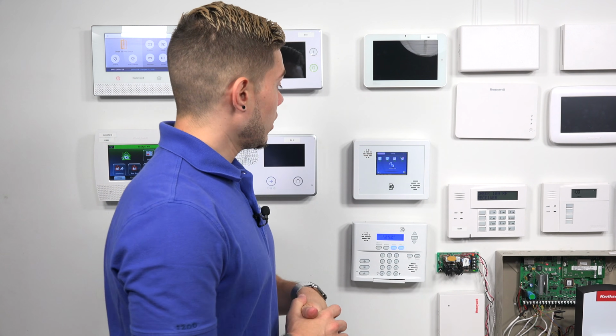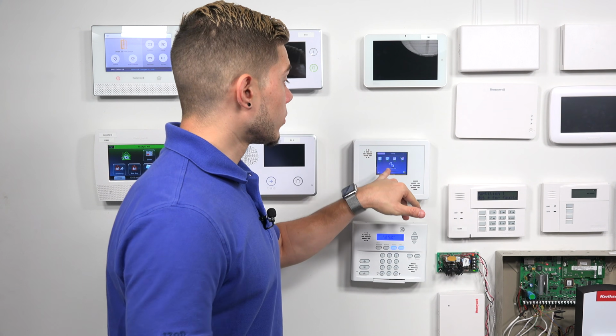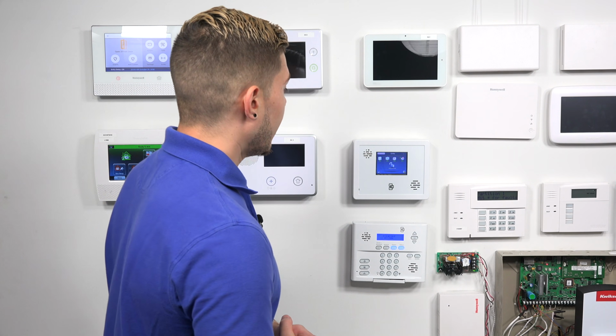As soon as I plug it in, you'll see the system goes back into normal mode. Now, keep in mind, why didn't it power on when you plugged the backup battery in? These systems need AC power to power on first, so even if you plug the backup battery in while the system is powered down, it will not power on. As soon as you plug in the AC transformer, this is going to turn on.